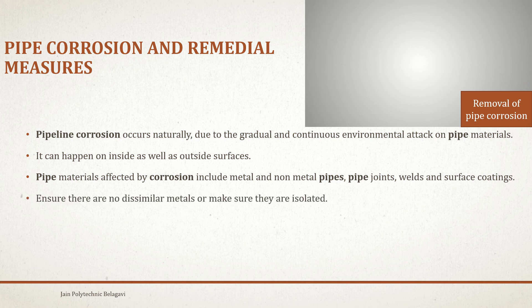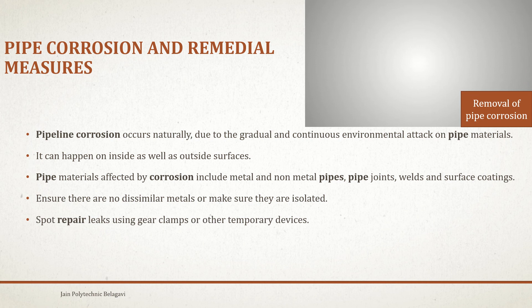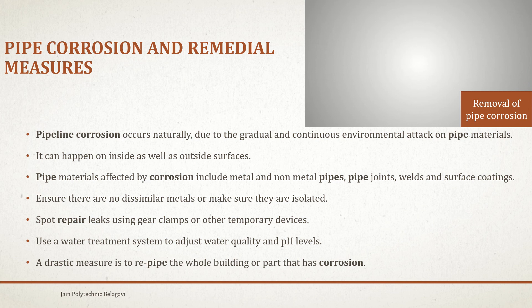Remedial measures include: ensuring there are no dissimilar metals in contact, or making sure they are isolated; spot repairing leaks using gear clamps or other temporary devices; using a water treatment system to adjust water quality and pH values. A drastic measure is to repipe the whole building or the part that has corrosion.